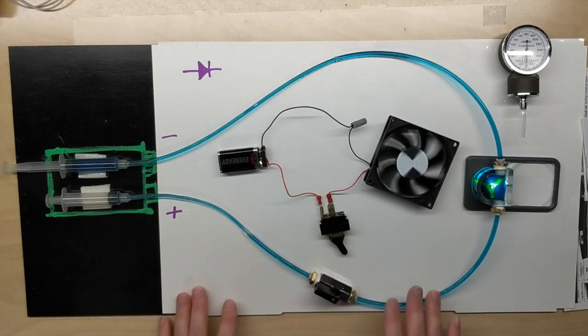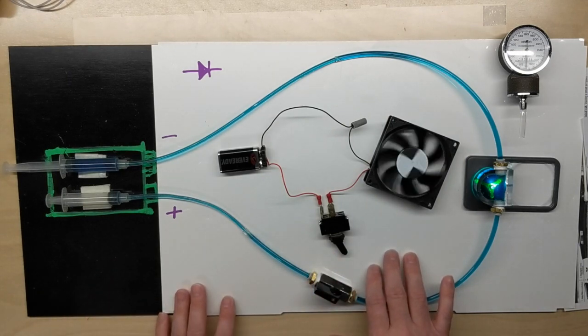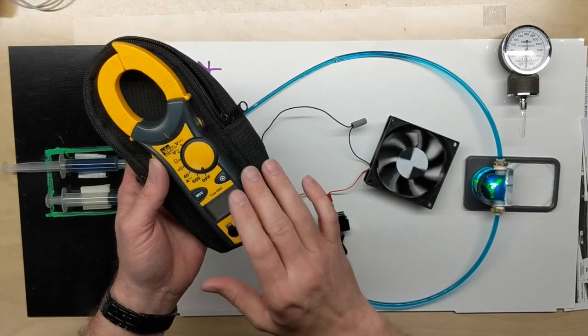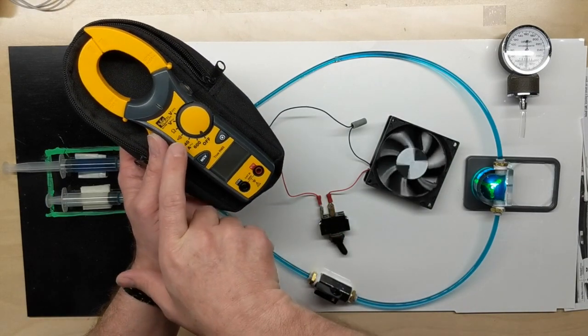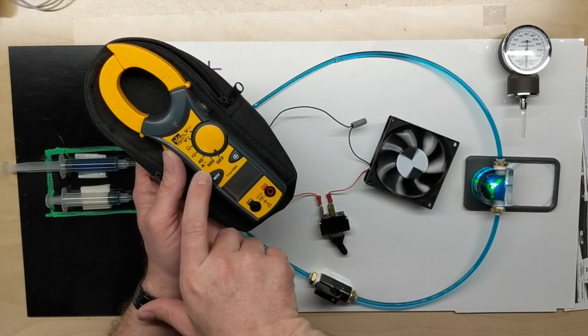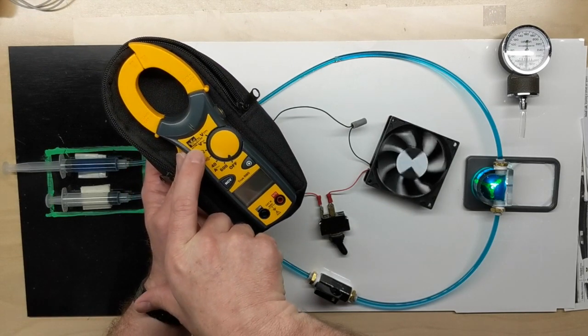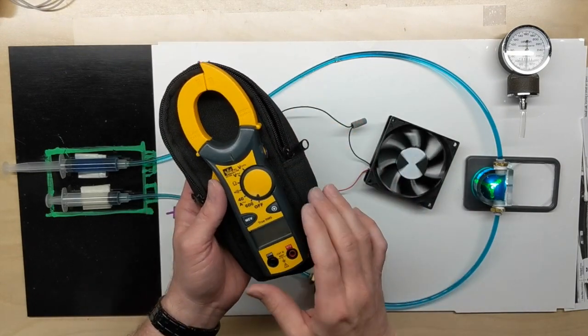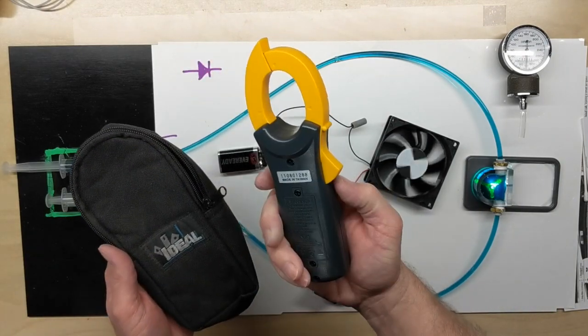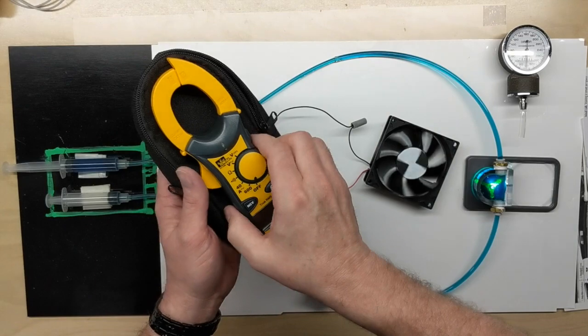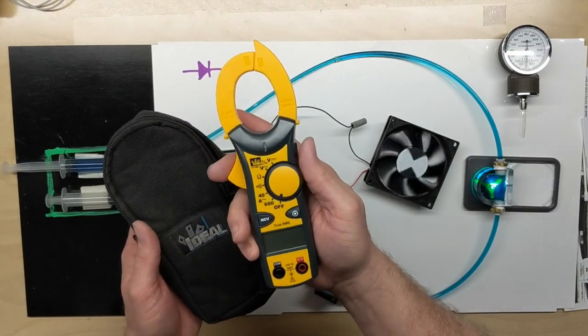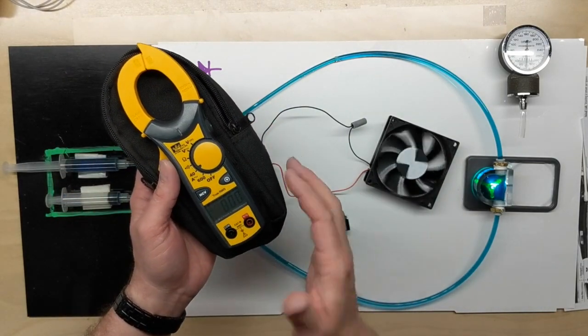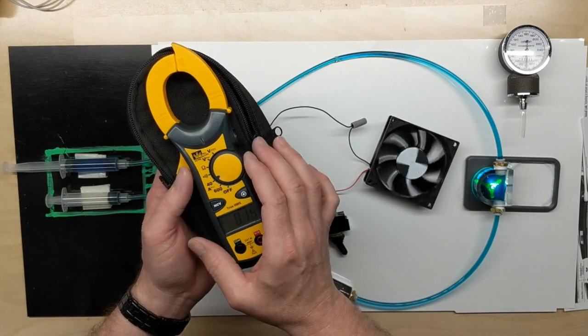Well, it can be easily measured with something like an amp meter. For example, for larger circuits, it's very nice to have an amp clamp. This meter will actually do more than one feature. It will do ohms, continuity, it'll do amps AC, it'll do voltage AC and DC. It also has a non-contact voltage alert on it as well. But this is actually made for AC. So household stuff, if we're in the breaker panel, we could actually clamp on and very easily tell the current of that circuit just by switching it to the actual position that we need.